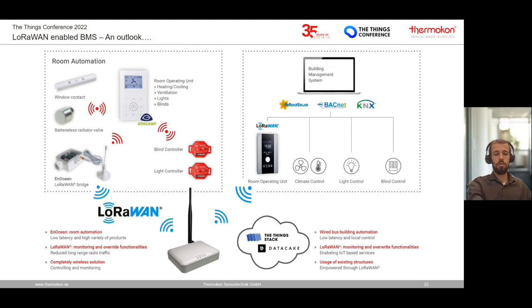As shown before, there are many communication systems in a building, and we've shown the approach for a traditional wired system, but this approach is also possible for a wireless system. In building automation, an EnOcean system is very commonly used, often in single room automation applications. That means we have a wireless room application where the whole control is done inside the room. You have one single controller that interacts directly with the actuators, like a radiator valve, a blind control, or light control.